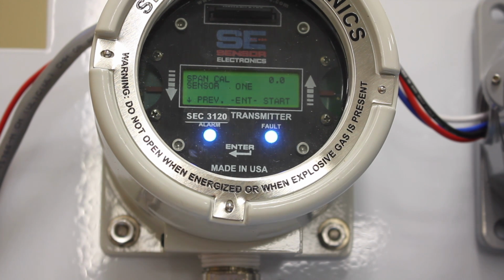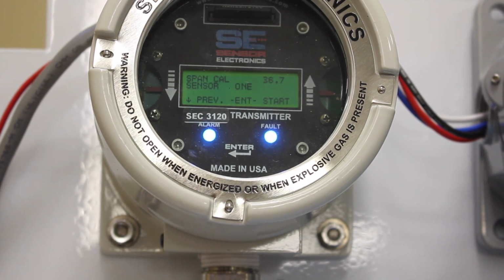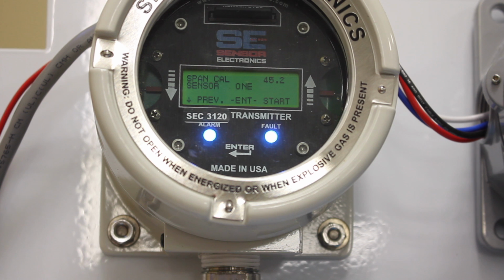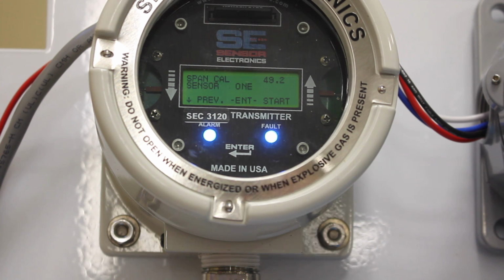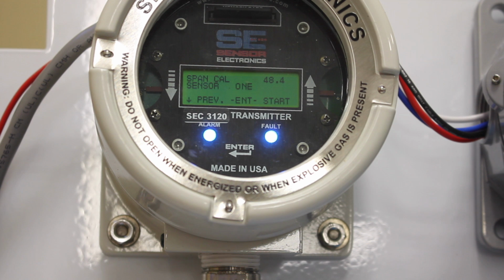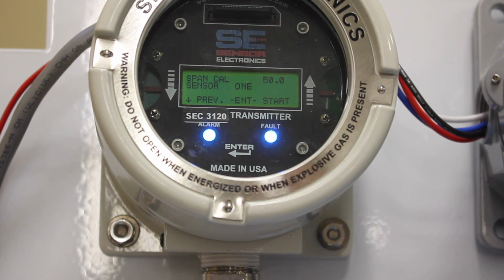And typically we flow 1 liter per minute calibration gas flow to the sensor. So I'm opening up the gas cylinder, and as the sensor starts reading gas, you'll see its actual gas reading in the upper right hand corner. And this reading may or may not go up to the 50%, but once you span it, it'll actually tell the sensor that you're applying 50% and change that reading to 50% LEL. So you just flow the gas for a minute or so and let the reading stabilize. So right now it's toggling between 49.2 and 50, so the sensor's within calibration, but we'll span it anyway.